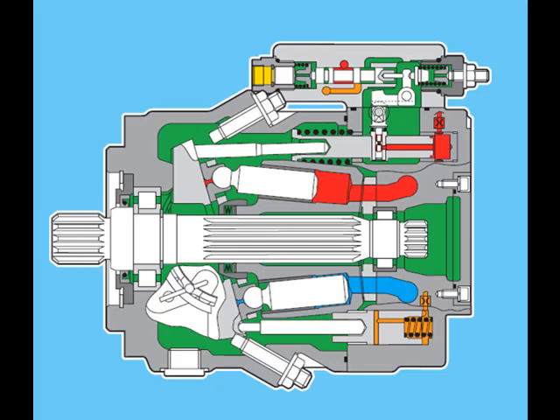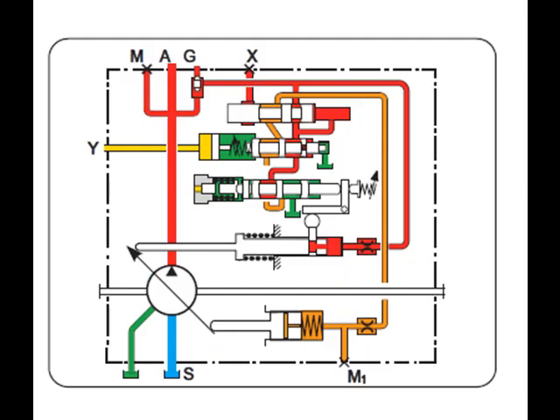The power control overrides the stroke limiter control; below the hyperbolic power characteristic, the displacement is controlled by the control current or pilot pressure. When exceeding the power characteristic with a set flow or load pressure, the power control overrides and reduces the displacement following the hyperbolic characteristic. To permit operation of the pump displacement control from VG max to VG min, a minimum control pressure of 30 bar is required for the electric stroke limiter LRU1-2 and the hydraulic stroke limiter LRH2-6.